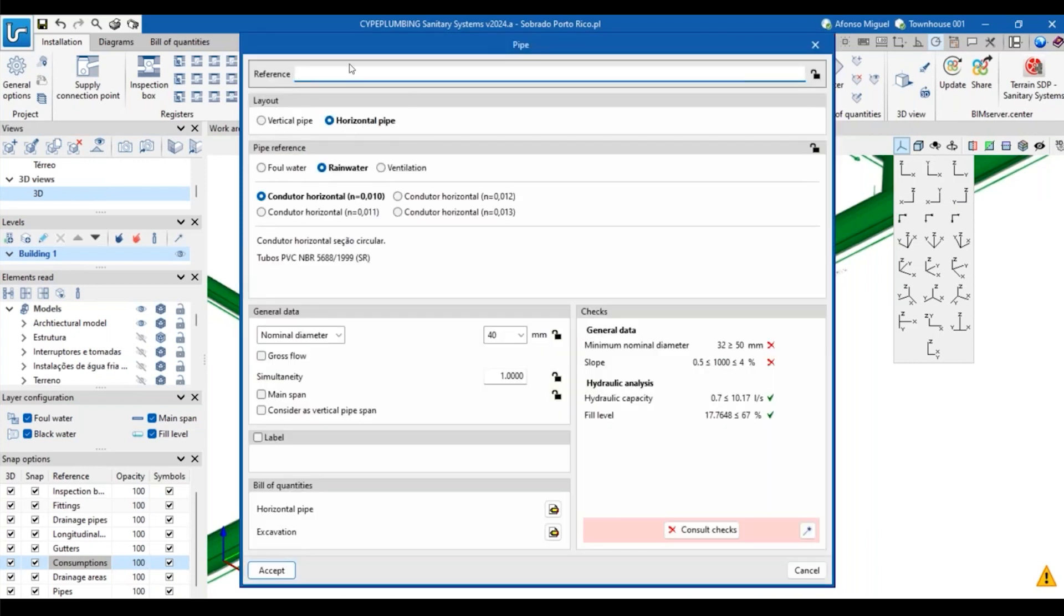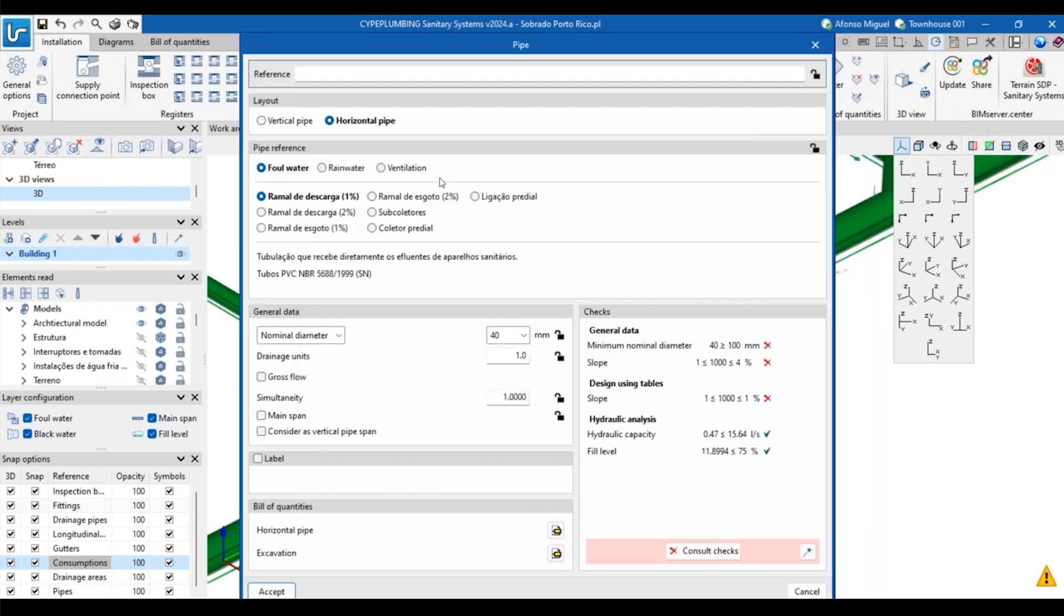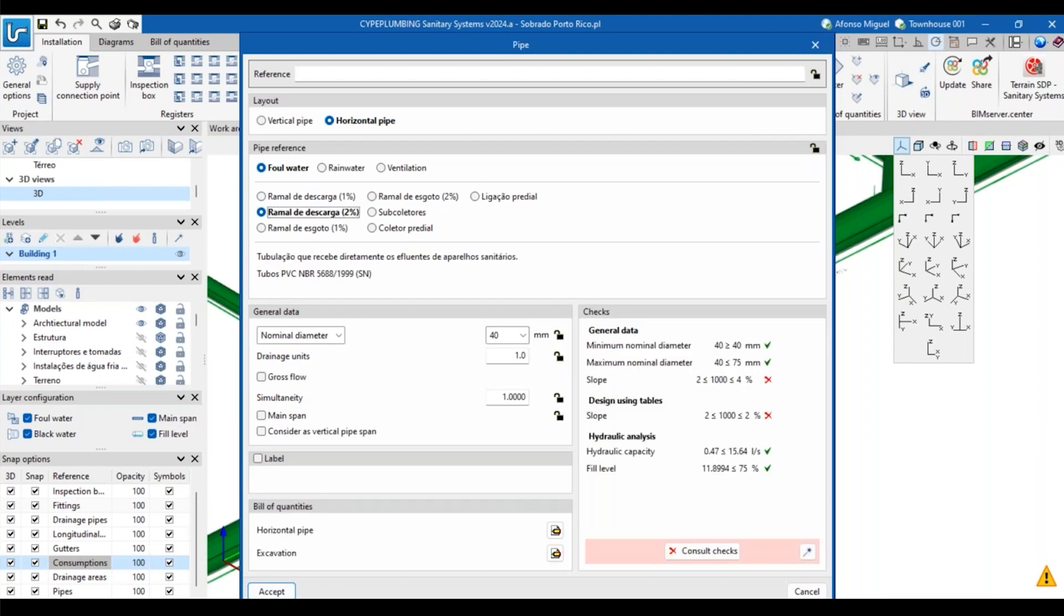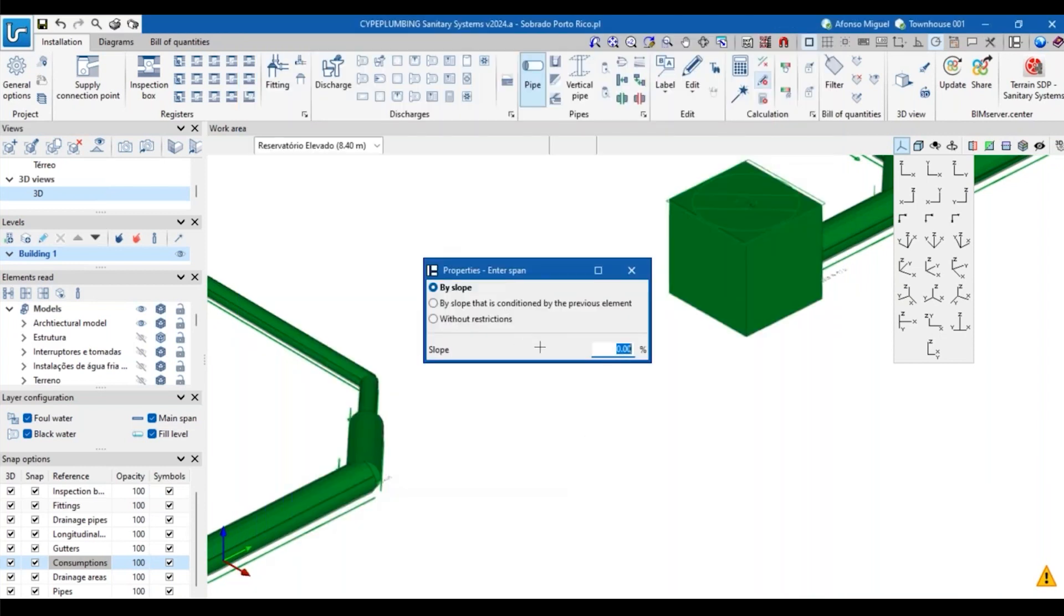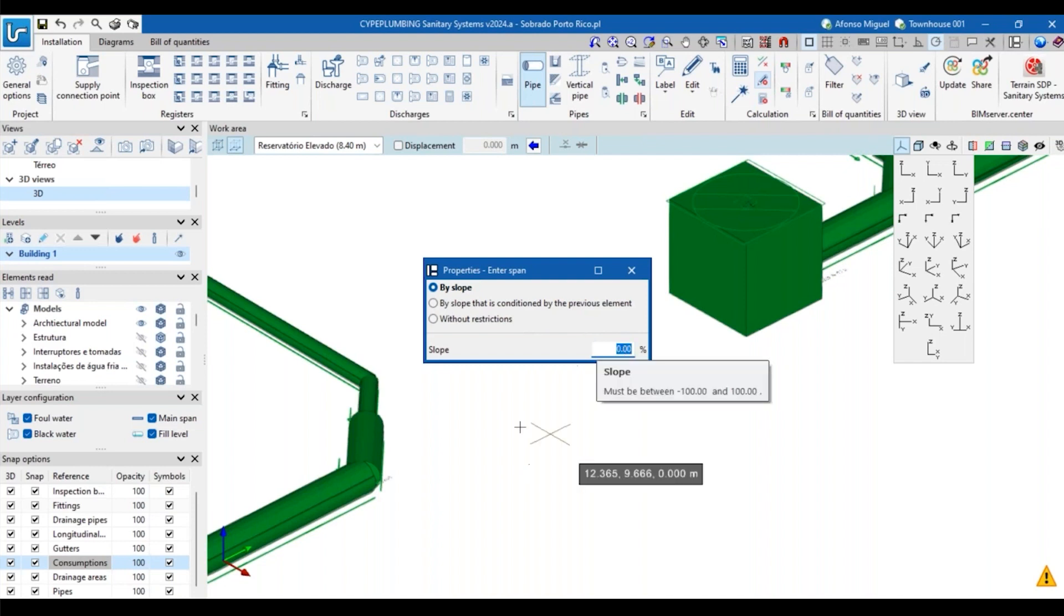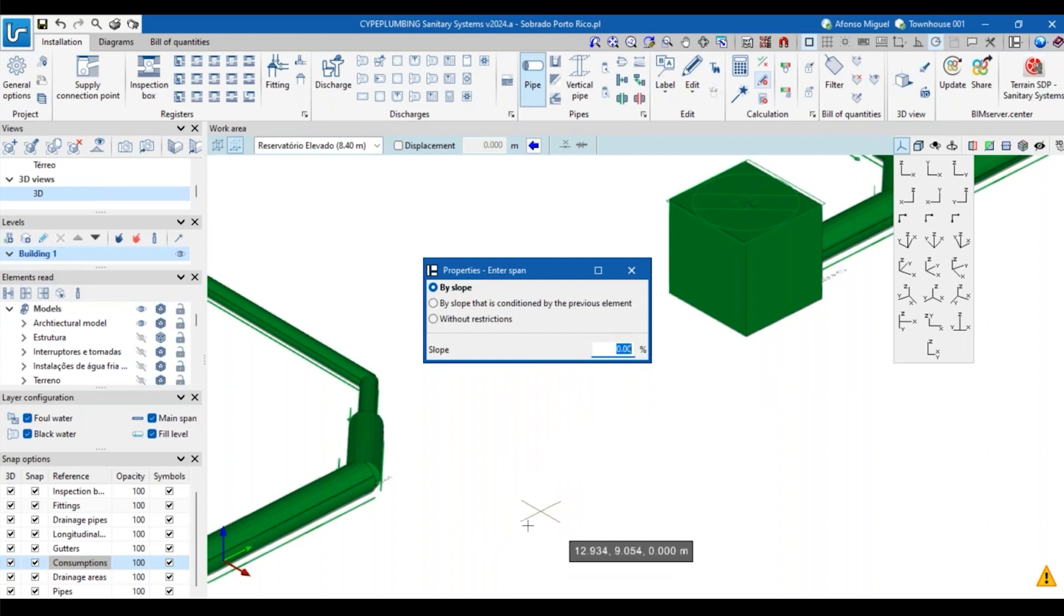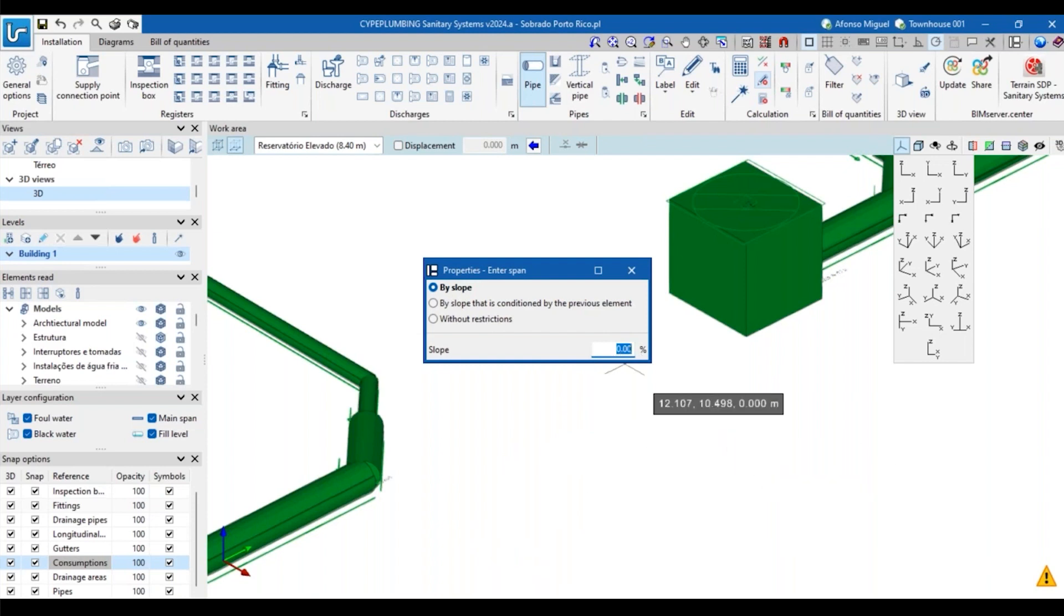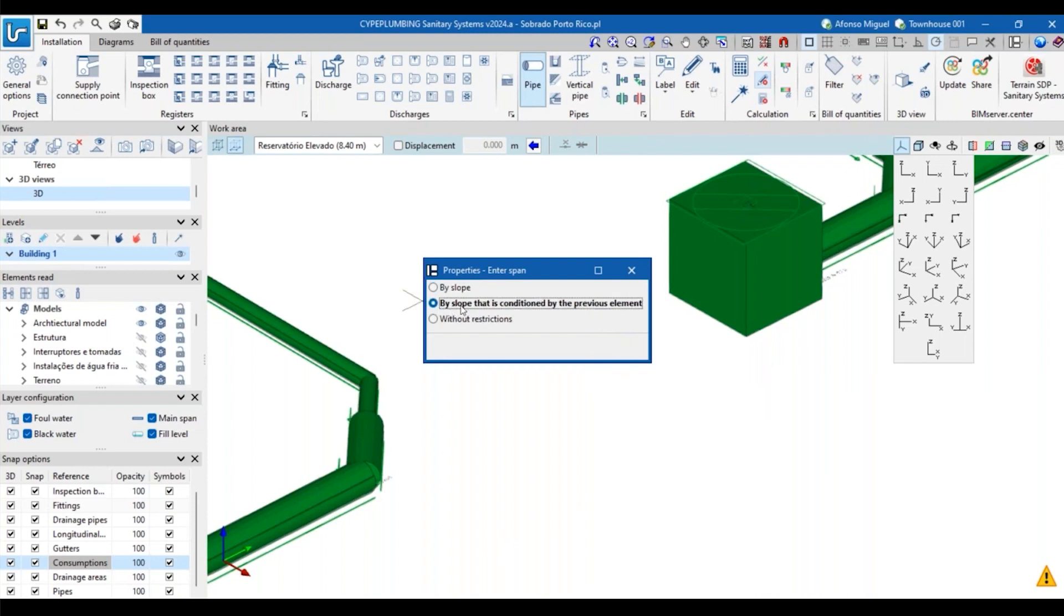To introduce a pipe here, you just have to use this pipe option. I will select one of the pipes that I've loaded before according to the code that I selected. There are different types of pipes that I've already loaded. I will take one of them and then I will define if I want to introduce this piece of pipe defining a specific slope, for example a fixed slope. If I use this option, I just have to add the pipe from one point to another and according to this value the slope will be introduced. I can select this option by a slope that is conditioned by a previous element.